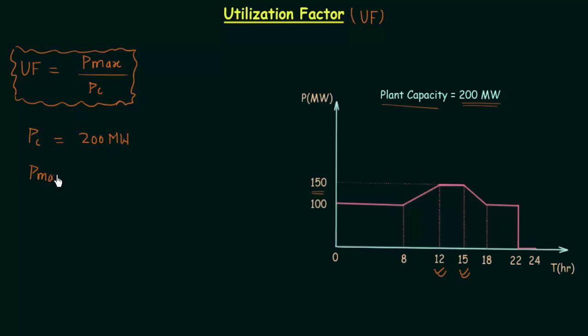So P maximum is equal to 150 megawatts and now we will find out the ratio which will give us the utilization factor. So 150 megawatts over 200 megawatts. The unit will be nothing because it is a factor. Megawatt megawatt will cancel out and when you solve it you will get 0.75.